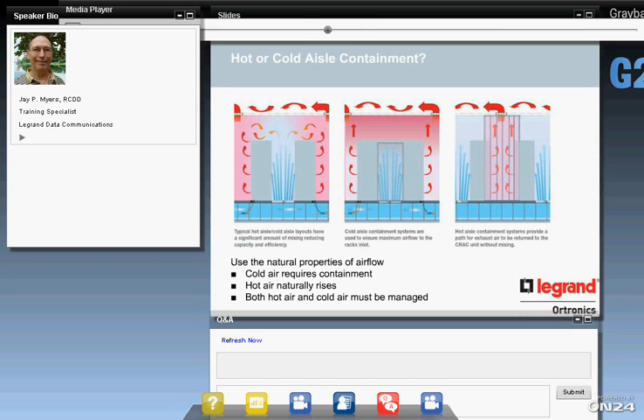If we let the hot air flow over top of the aisle and mix with the cold air, we are diluting that cool air that we spent a lot of money cooling. And a little bit of a hidden cost also is if we let the cold air dilute the hot air and the air going back into the CRAC unit is not as hot, that reduces the efficiency of those units greatly. So we can use the natural properties of the air pretty easily. Cold air is denser, and if we can close off the ends of the aisles with some kind of door or curtain, that keeps the cold air from just flowing out the end of the aisle. That cold aisle will fill up like a swimming pool. The hot air tends to be lighter and naturally rises, so as long as we provide a good pathway for it, it'll end up back at the CRAC unit where we want it, as hot as possible. So we really have to manage both.